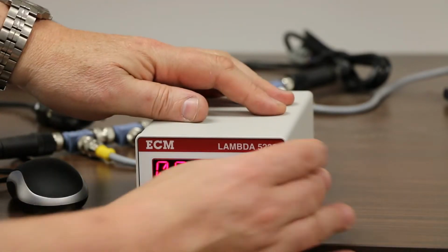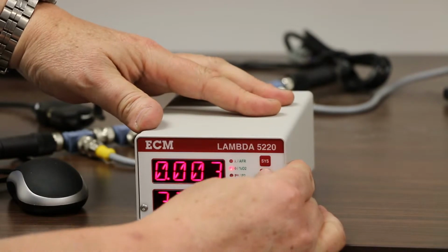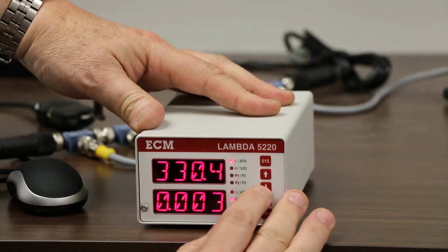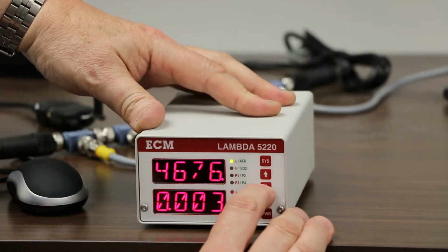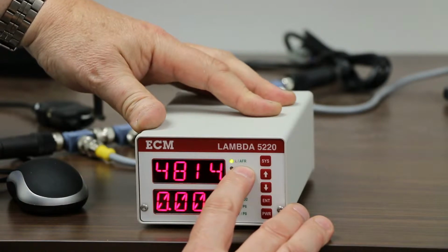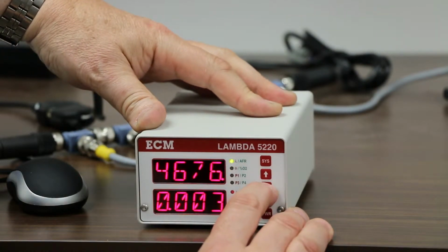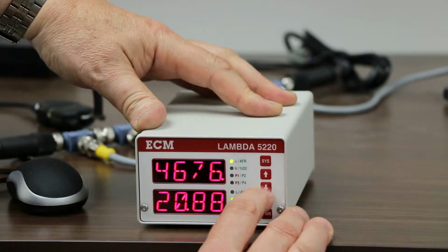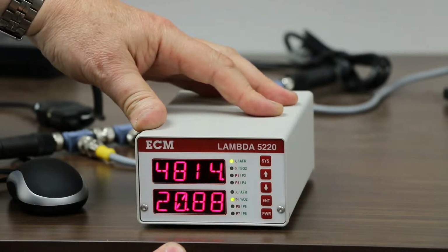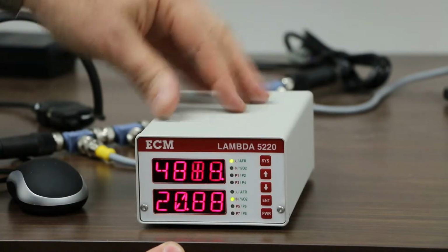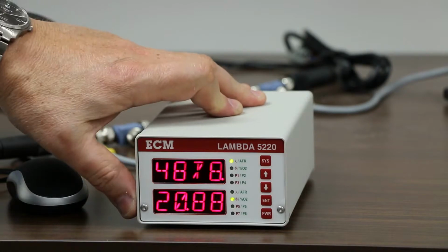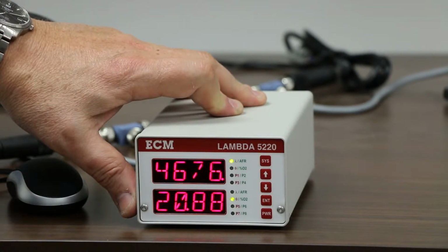To set the display is very simple. You just press these up and down arrows, and here the green one is air fuel ratio. So air fuel ratio is one parameter that's been selected. You press enter and you go down to, in this case, percentage O2. This will be a nonsense air fuel ratio number because the simulator is simulating air. So we've set 2 of the parameters that are going to be sent down the CAN bus.